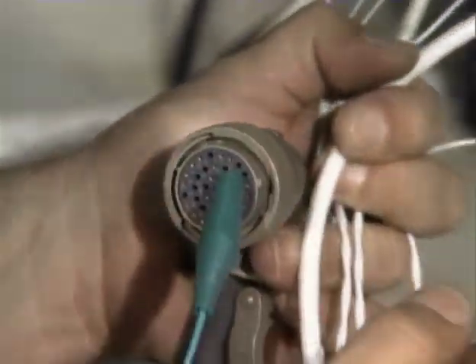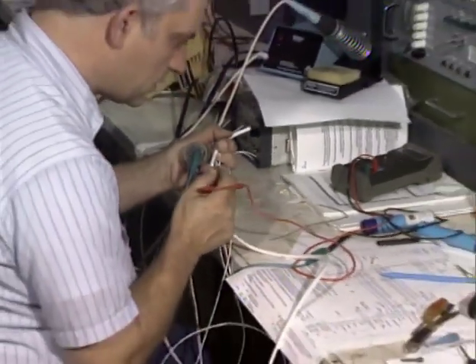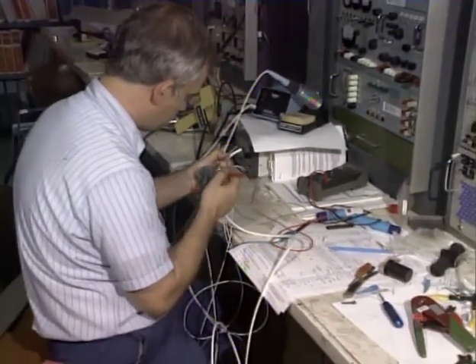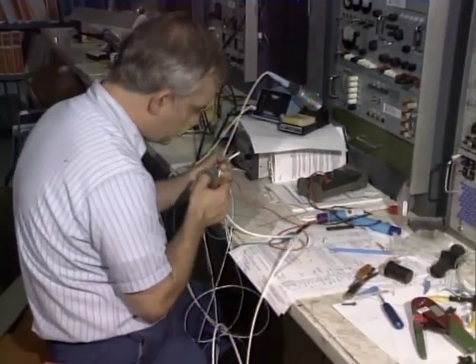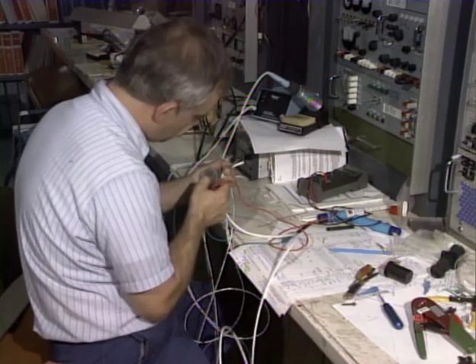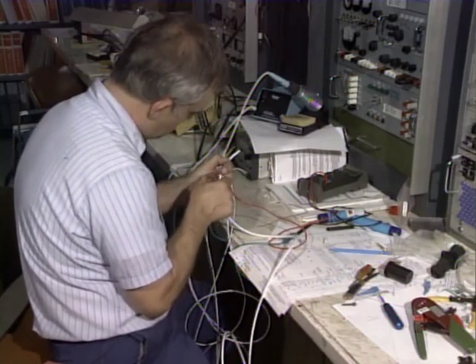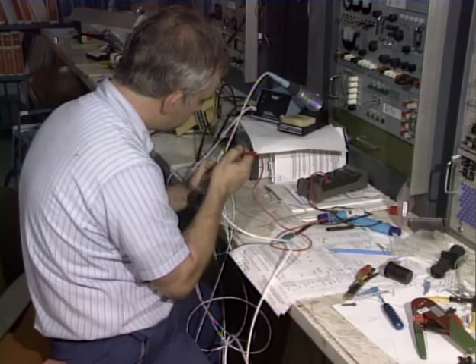Now, the FAA wants you to know about electrical equipment adjustments and overhaul. Major adjustments on equipment such as regulators, contactors, and inverters are, according to the FAA, best accomplished outside the airplane on test benches with the necessary instruments and equipment, using adjustments, procedures, and so on as outlined by the equipment manufacturer. And you cannot go wrong following the manufacturer's recommendations because the FAA must approve the manufacturer's recommendations.